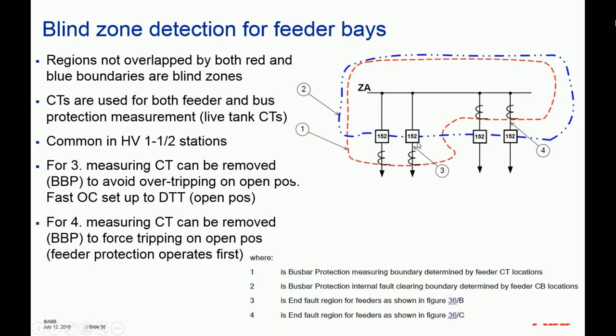So for the fault strike here, as you can see, by the way, this type of design is very common for high voltage breaker and half stations, right? So this is your dedicated bus, for example, and this is one of the bus breakers, for example. When the fault strikes here, the measuring CTs, the bus will operate. Okay, the bus definitely will operate. However, the fault is not cleared, right? Because the contribution, the source from this side will still continue energizing the fault.